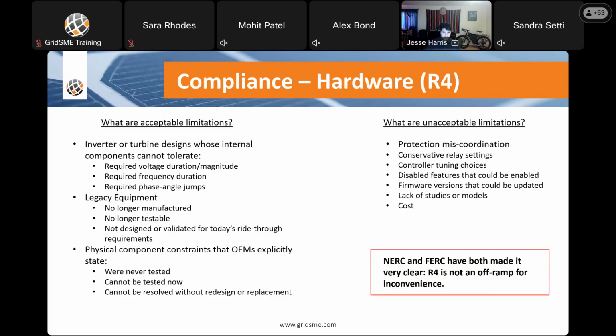So here we are back at hardware, R4. To comply with this, acceptable limitations are inverter or turbine designs whose internal components cannot tolerate required voltage duration, required frequency duration, required phase angle jumps. You could have a facility that has legacy equipment that's no longer manufactured, or the OEM is just completely out of business, no longer testable, not designed or validated for today's ride-through requirements. Or you could have physical component constraints that the OEMs explicitly state were never tested, because how would they have known PRC-029 was going to be in effect? And they can't be tested now and can't be resolved without redesign or replacement.